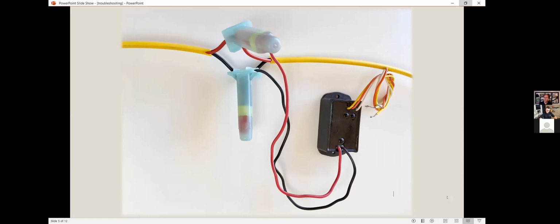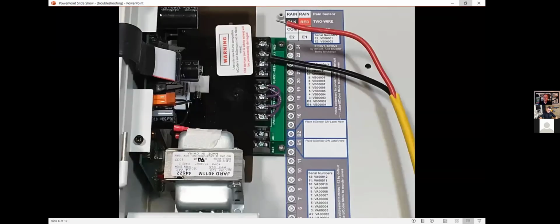Absolutely correct. There is a slight possibility that the controller could be the issue. So one of the first steps is to disconnect the wire path from the controller. Here I just pulled off the red side of the wire path. That's all we needed. Then if that error message goes away, that means my wire path connection went away, so the problem has to be in my wire path. If that error message persists, it could be in the board, and then I need to talk to support and might need to change it out or do some other troubleshooting on the controller.